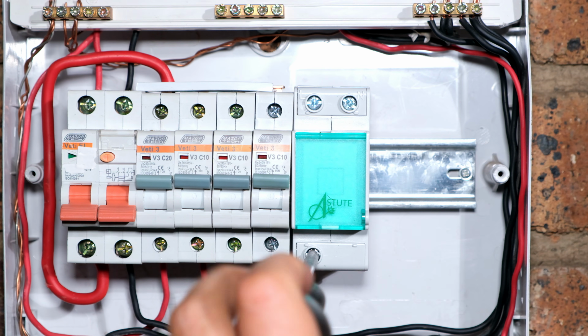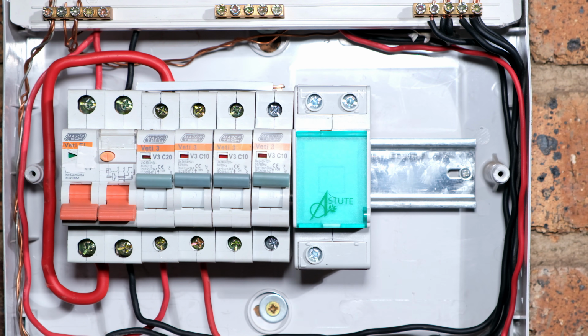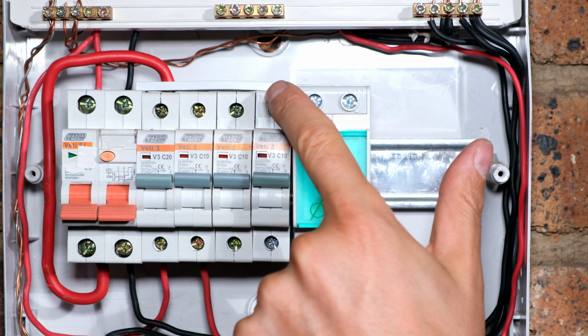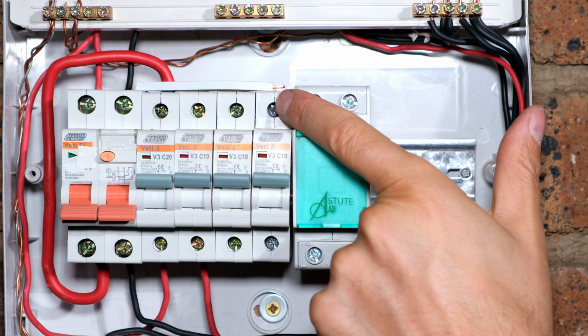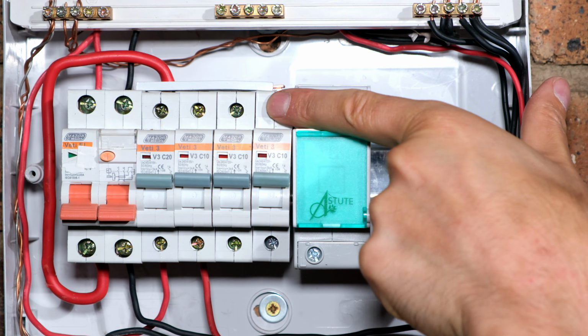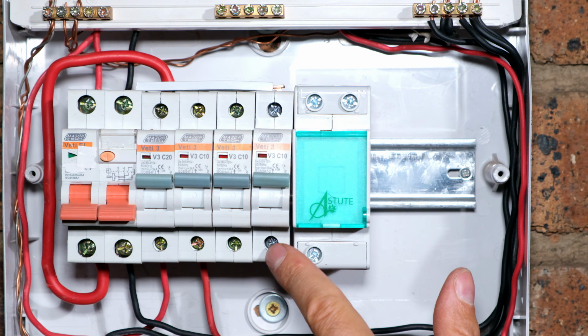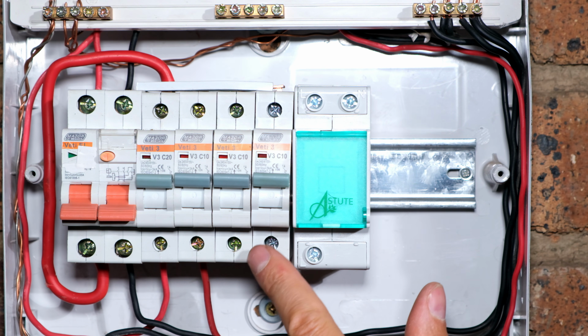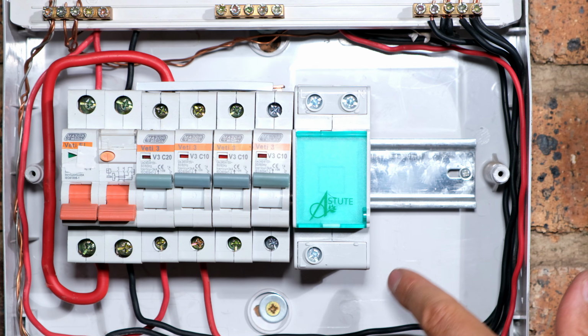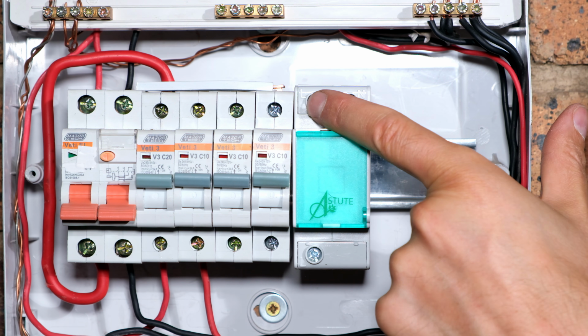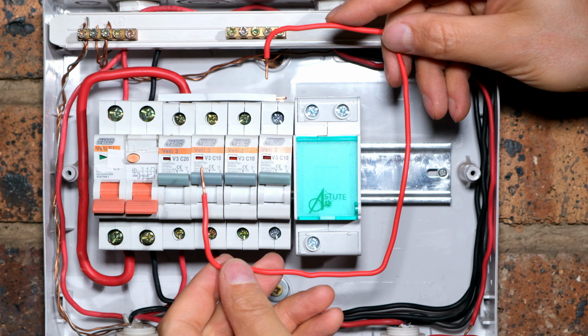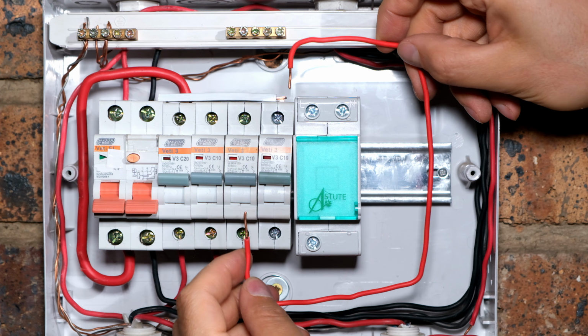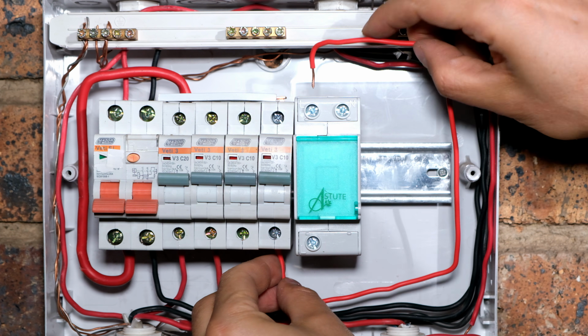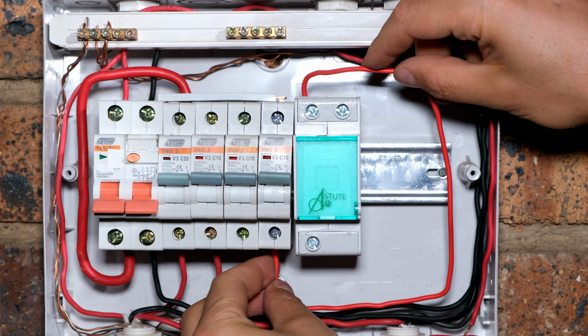I'm just going to loosen these screws, and I'm going to start with the live wire. So the top of the circuit breaker already has live. Remember, it's coming from this top rail. And now we're going to go to the output of the circuit breaker, which is the load side. So I'm going from the output of the circuit breaker to the input here, the live at the top of the timer. All right, I've taken a wire and I have formed it into this shape. And the reason for that is I'm going to go from the output of the circuit breaker to the input here, the live of the timer.